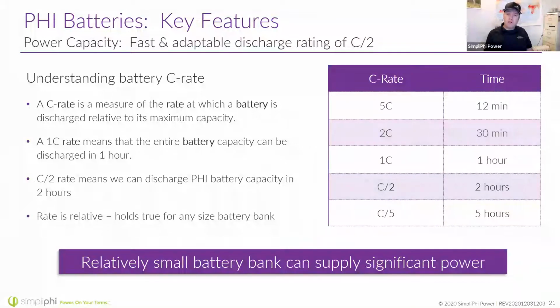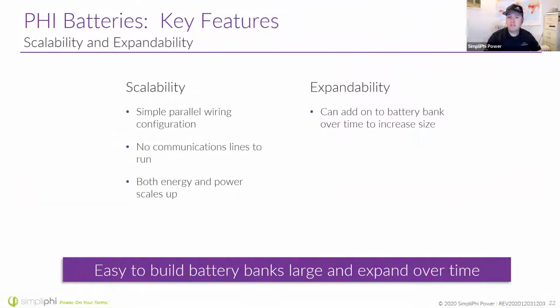So it's important to note that our batteries—75 amp hours at 48 volts for the Phi 3.8—are rated at that C over 2 rate. The takeaway is that you can charge and discharge this battery relatively quickly, taking advantage of power when you have it, and also discharge it quickly to support the loads it needs.